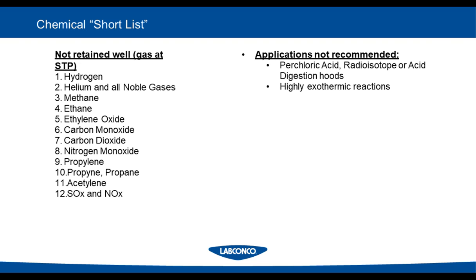One thing to remember about filtered ductless hoods is they do not remove heat from the laboratory. Unlike a ducted hood, which would exhaust that heat right outside, filtered hoods would not. They would return that heat right to the lab itself. Again, really not a problem for your teaching classes. You're usually working with smaller amounts. You can absolutely use Bunsen burners in these hoods and heat your samples and whatnot.